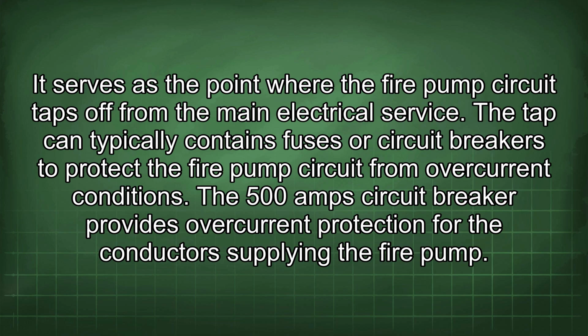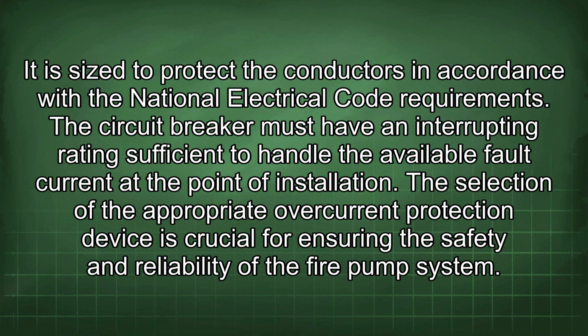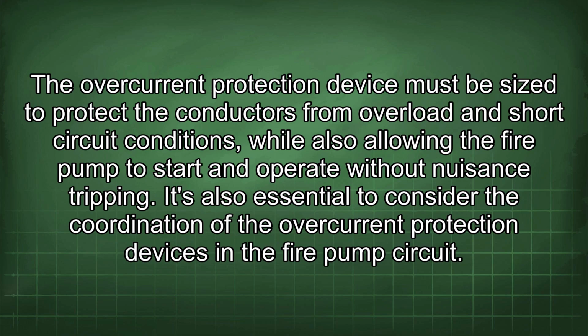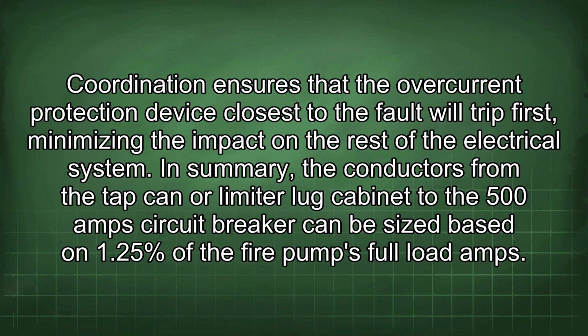The 500 amp circuit breaker provides overcurrent protection for the conductors supplying the fire pump. It is sized to protect the conductors in accordance with the National Electrical Code requirements. The circuit breaker must have an interrupting rating sufficient to handle the available fault current at the point of installation. The selection of the appropriate overcurrent protection device is crucial for ensuring the safety and reliability of the fire pump system. The overcurrent protection device must be sized to protect the conductors from overload and short-circuit conditions, while also allowing the fire pump to start and operate without nuisance tripping. It's also essential to consider the coordination of the overcurrent protection devices in the fire pump circuit. Coordination ensures that the overcurrent protection device closest to the fault will trip first, minimizing the impact on the rest of the electrical system.